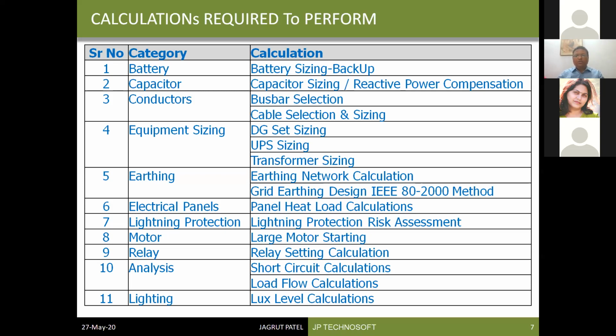For a large motor, we should know what the behavior is during the starting of the motor. As we all know, during motor starting, it takes much more current, which is called inrush current, something like 6 to 7 times the rated current of the motor. So during the starting period of the motor, some dynamics will be there, which we need to understand. That is called motor starting calculations. Then there will be relays and protection circuits, so knowing the setting of the relay is a must. Load flow and short circuit analysis is a must for any project. And then finally there is lighting, so lux level calculation for an area is a must. So these are the calculations which are required to perform for a project.